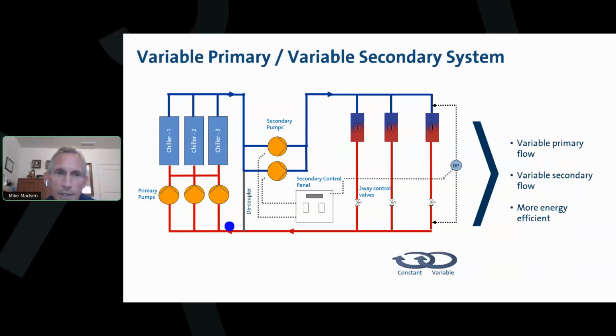The other one we see out there is called variable primary, variable secondary. Sort of an improvement in my mind because you've got smaller primary pumps. Their only job is to keep the chillers happy, and we've got a decoupler. There's no valve or check valve in the decoupler, and so the primary pumps keep the chillers happy and keep chilled water available for the secondary pumps to pull from. The secondary pumps are still fairly high head because they need to produce enough head to satisfy that furthest zone again, that index zone, where we're maintaining some delta P.